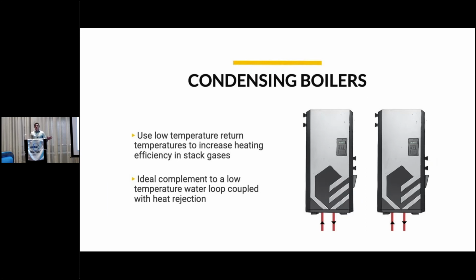Our condensing boilers were designed and chosen because it's a really great way to install a resilient gas burning solution while capitalizing on a very low temperature hot water network. It works really well with the hybrid fan coils that we designed, because if we operate our condensing boilers at a low enough temperature, we're condensing in our stack, but because the heat rejected in the cooling mode is coming through, if we're in our shoulder season where we may want to heat some apartments, because it's such a low temperature, we may not even have to fire up our condensing boilers to keep that system warm.